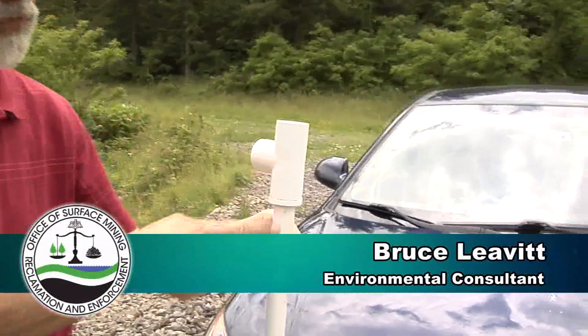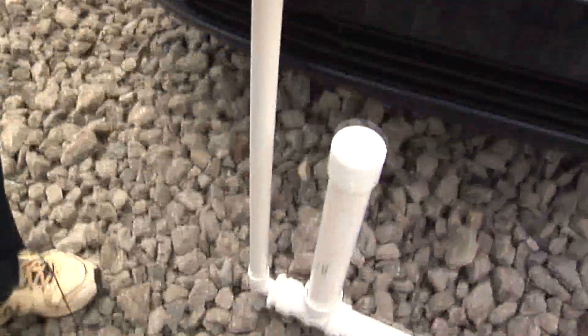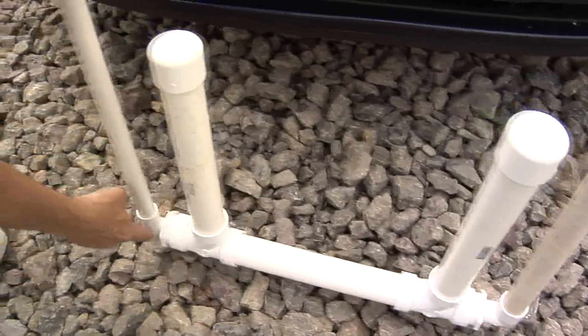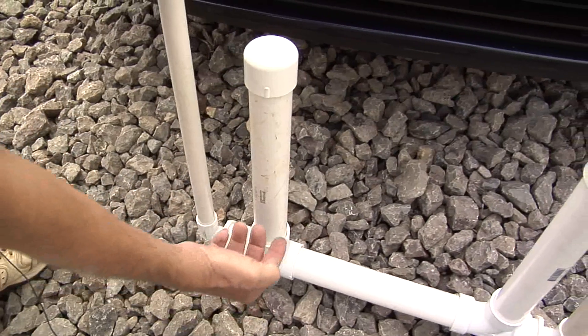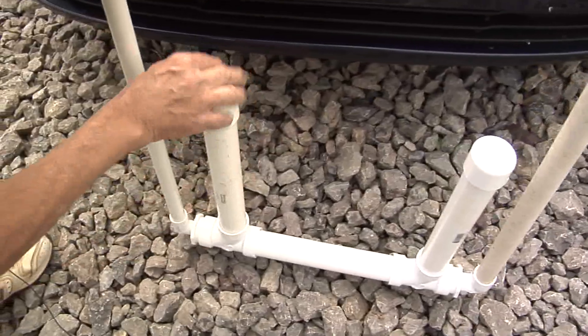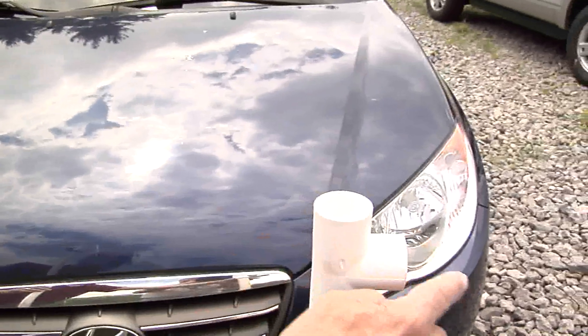Water comes in here and falls down this vertical pipe. At the same time, air is entrained and the velocity of the water carries the air bubbles down to the bottom here where we change direction and the pipe enlarges. The air bubbles then float to the top and are captured in these reservoirs. The bulk of the air is captured in the first one and the remnants are captured in the second.